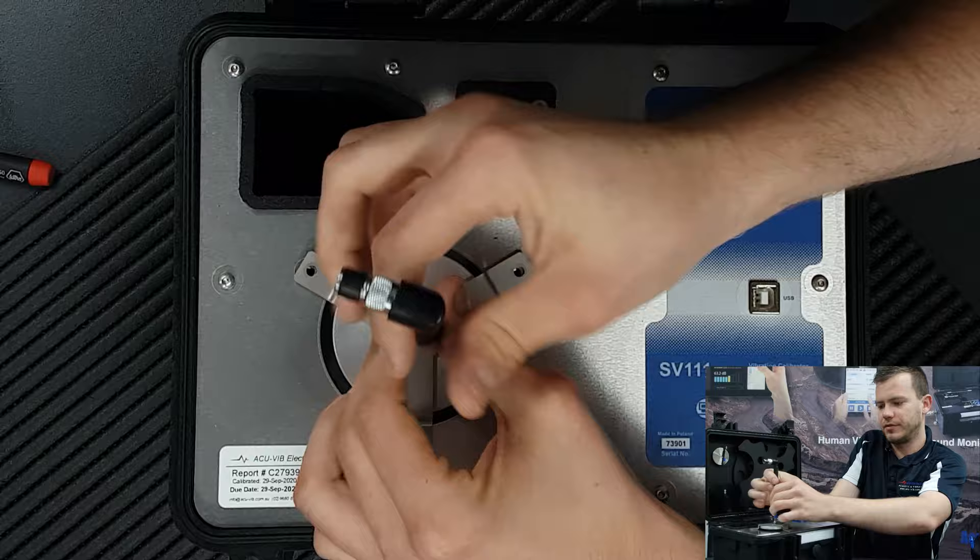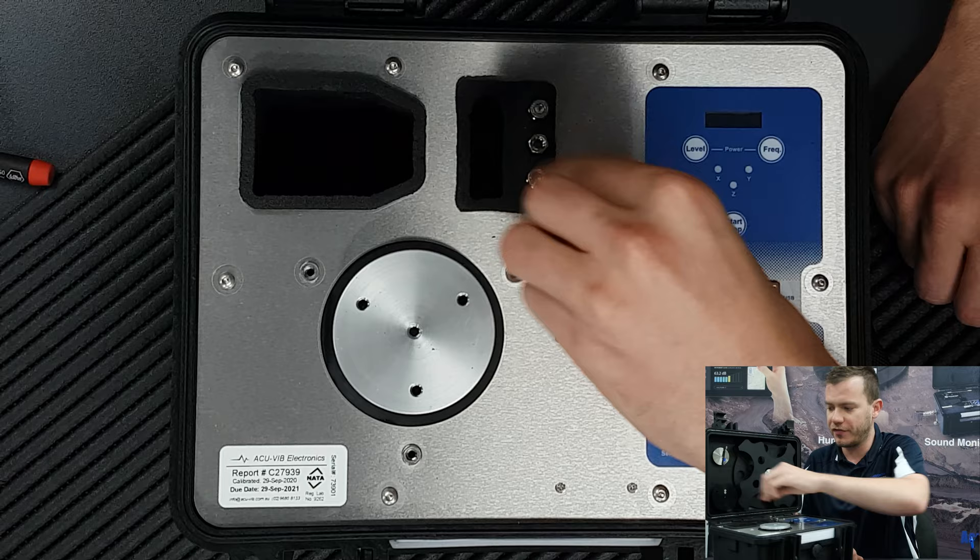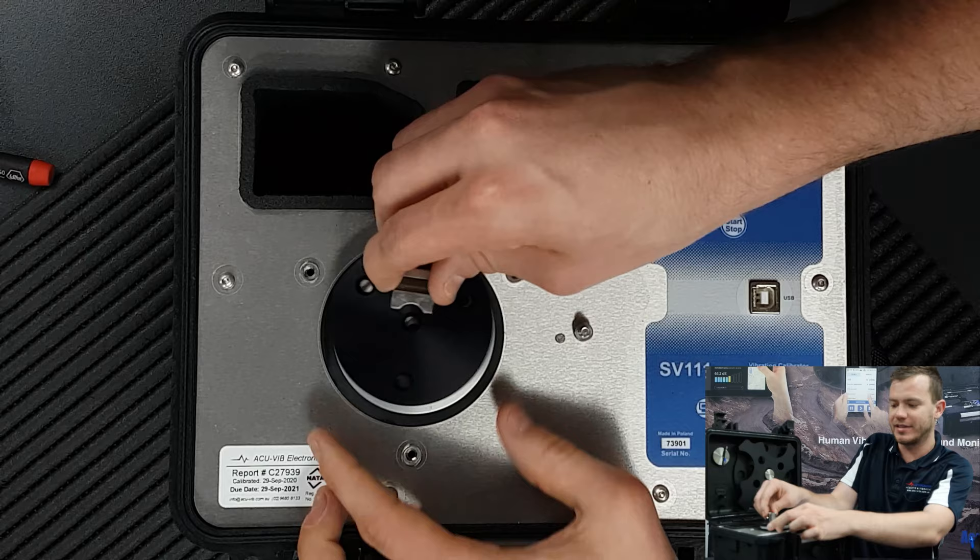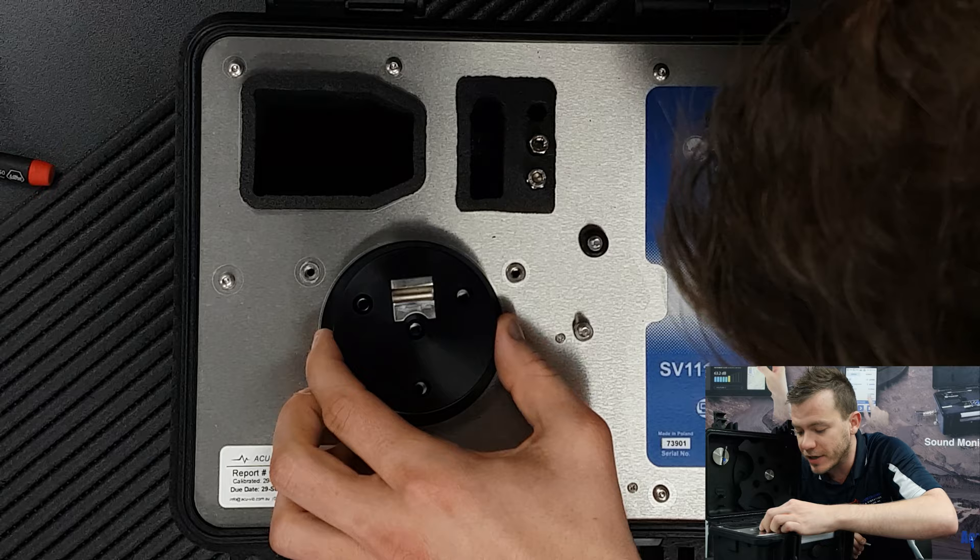Okay, now that we've got that dismantled, what we need to do is apply the base plate for the bracket for the whole body seat pad. If we just unscrew this, they fit into the case quite nicely and then you can see three holes lining up with the base plate of the vibration shaker. It's recommended to use as many screws as you want; for an in-situ check one screw in the middle should be fine, but for today's measurement I'm going to use three just to make sure we're not getting any resonance through that adapter.